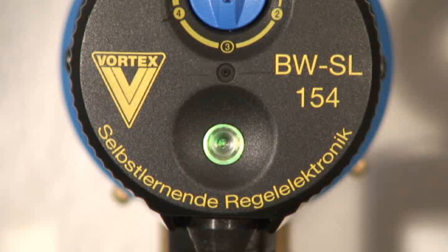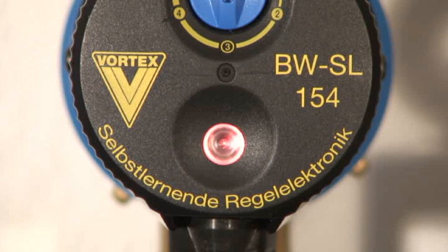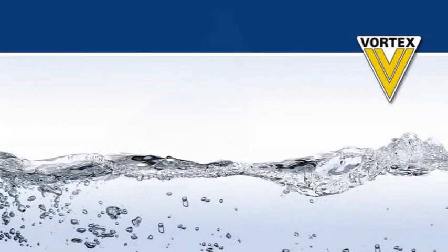A steady green light shows that the pump is running. A flashing green light shows that the pump is not running and that no hot water is needed. A green and red flashing light shows that the pump is running, but the non-return valve is not closed. The non-return valve needs to be replaced. A red flashing light indicates that, although the pump is running, the connection to the flow sensor is faulty. A steady red light indicates that the pump is not running. Either the pump is dry or the boiler is cold. Other possibilities are that the non-return valve is stuck closed or the flow sensor has come loose.